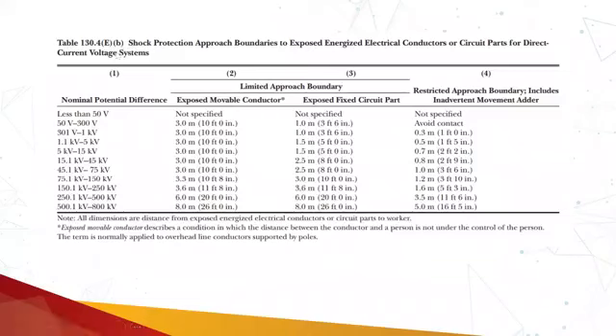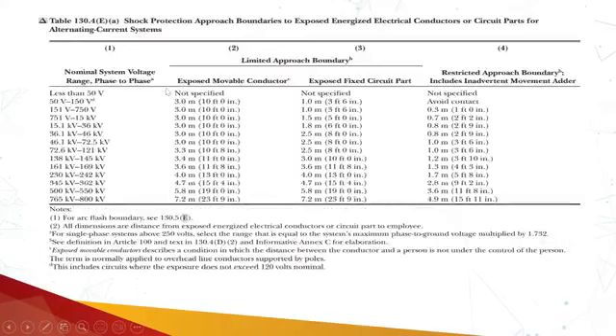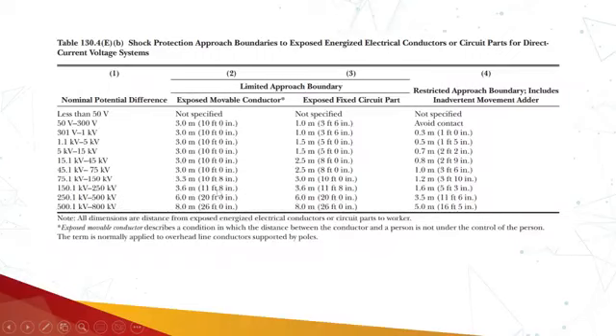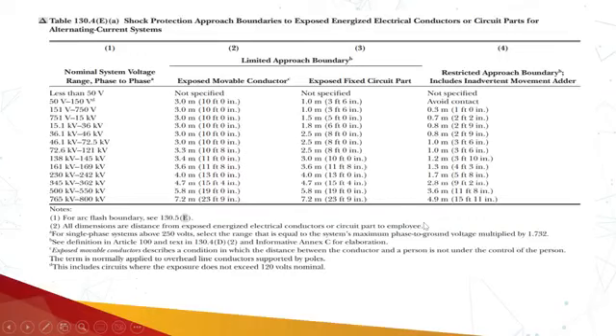For direct current, less than 50 volts is not specified. As the voltage increases, the limited approach boundary and the restricted approach boundary will also increase. We can have a comparison: for the AC system at 800 kV, the limited approach boundary is around 7.2 meters and the restricted approach boundary is 4.9 meters. And for the DC circuit, it's more: the limited approach boundary is 8 meters and the restricted approach boundary is 5 meters. So the increase in the boundaries for the DC system is more compared to the AC system.